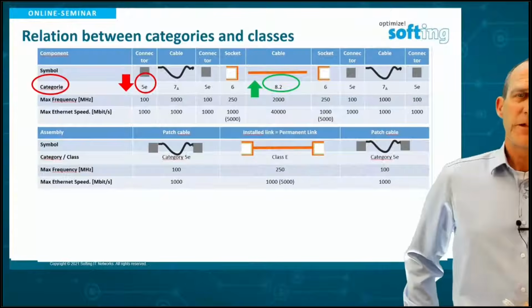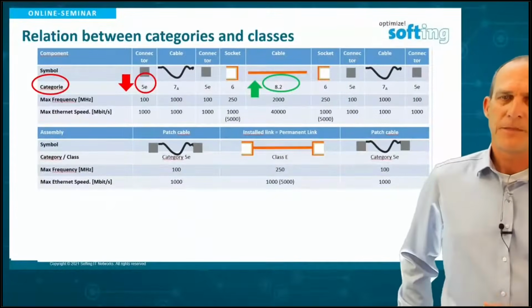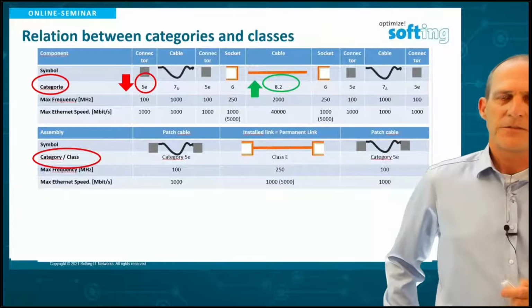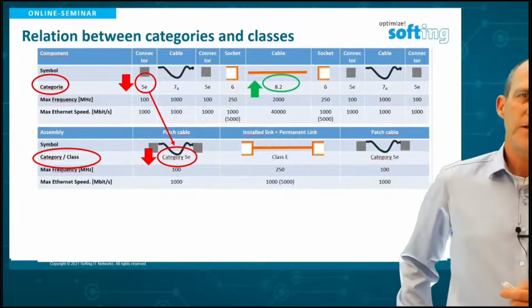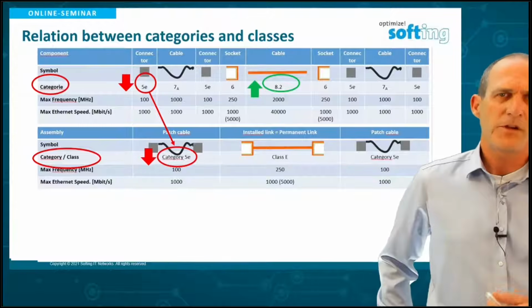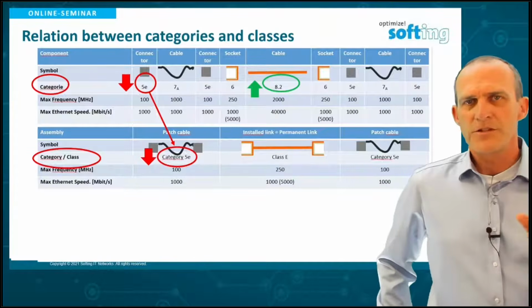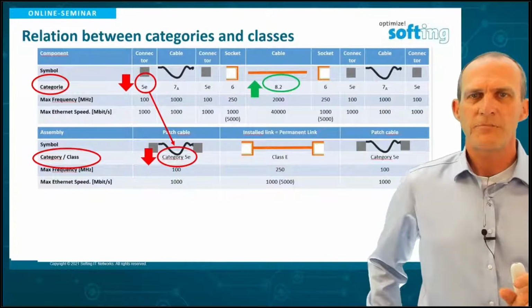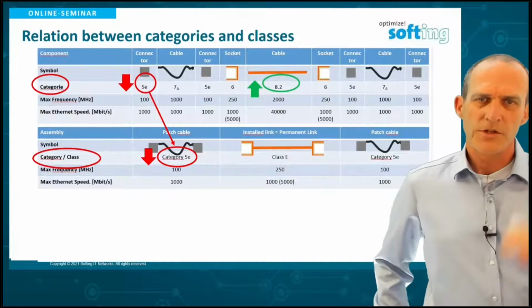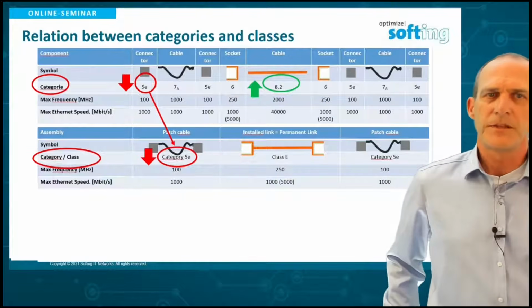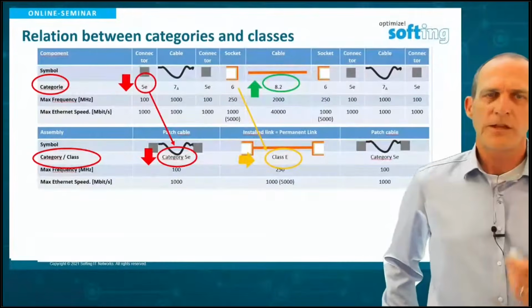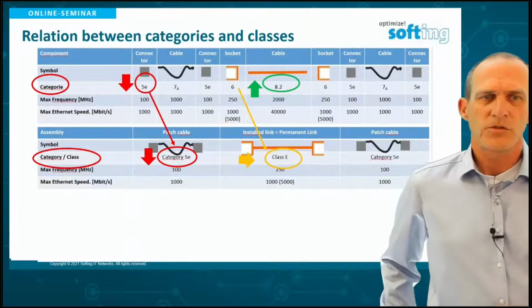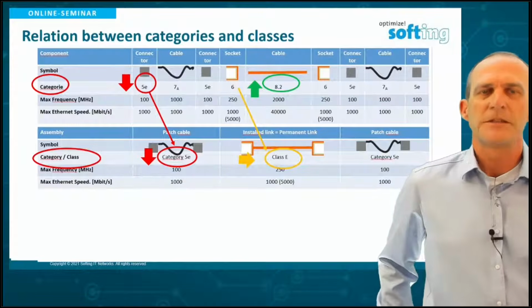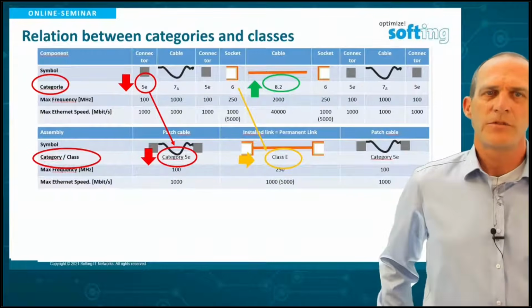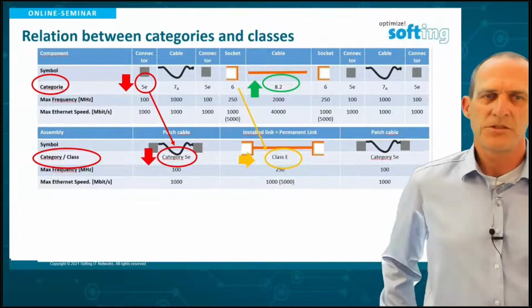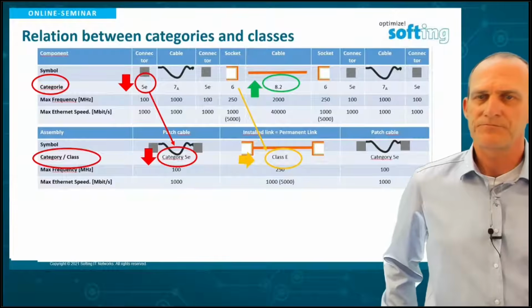Now I have built a patch cable and a permanent link. The patch cable is still a category 5E patch cable. Why category 5E? You used a 1000 megahertz cable, but the connectors at the end are only 100 megahertz connectors, so they slow the whole thing down to category 5E. Same with your link: your category 6 sockets slow your link down to a class E link, up to 250 megahertz. So the very nice category 8.2 cable used in this example isn't really utilized here. It's only a class E link.